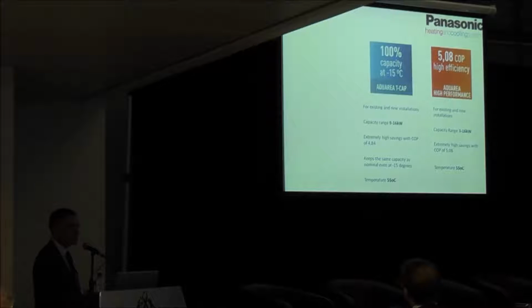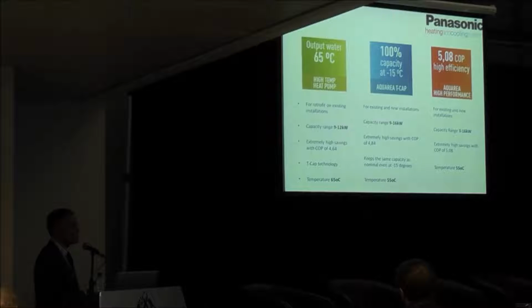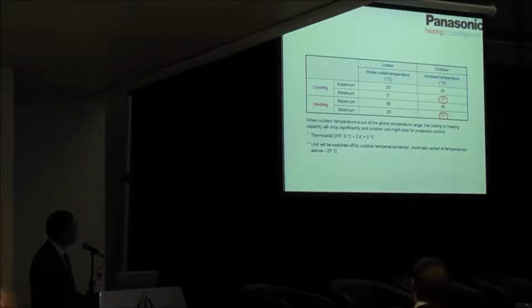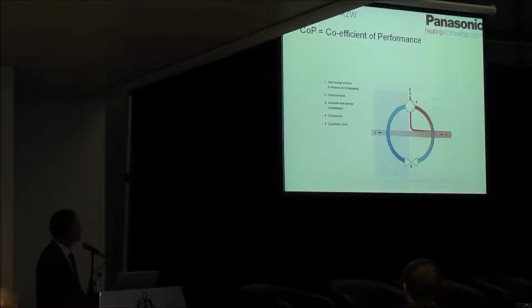There's the T-CAP units, which can guarantee heat outputs down to ambient of minus 15 degrees C. Capacity range 9 to 16 kilowatts. Again, high COPs, not quite as good as some of the standard units, and again a max flow temperature up to 55. And then we have high temperature units. There's water flow up to 65, but that's only available in 9 and 12 kilowatts. For heating, we can guarantee heat output down to ambient of minus 20 degrees C. But if we're utilising the heating and cooling units as well, we will only get cooling down to ambient of plus 16 degrees C. So it is only for comfort cooling.